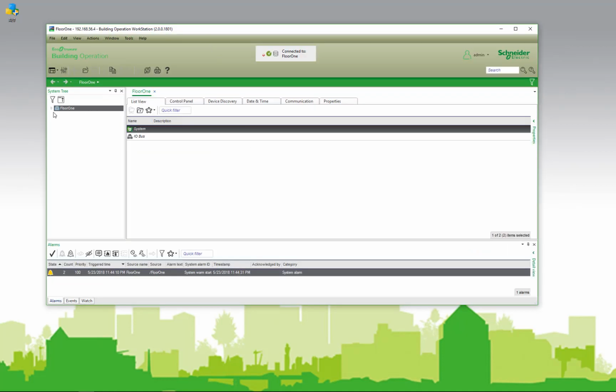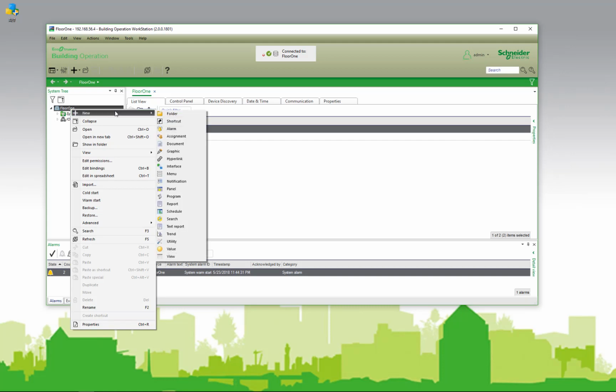So now our virtual ASB is open. One thing that I'll have to do is create a BACnet interface. Under this air handling unit, we're going to have the 10 VAV controllers. Those VAV controllers are the SmartX MP IP controllers. In order to add them here, I need a BACnet interface. One thing the AET is not able to do is create interfaces, so we'll do it manually in PCT now.